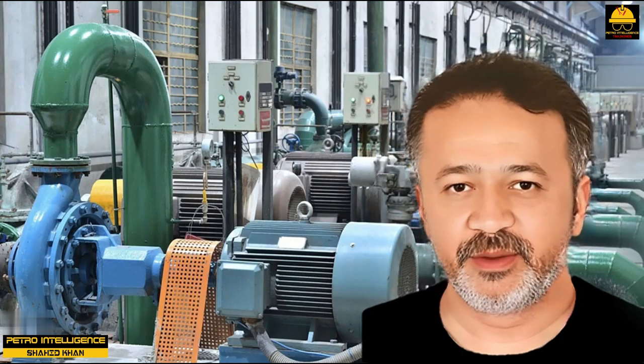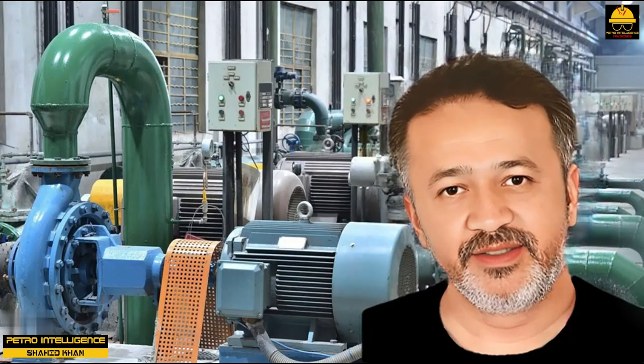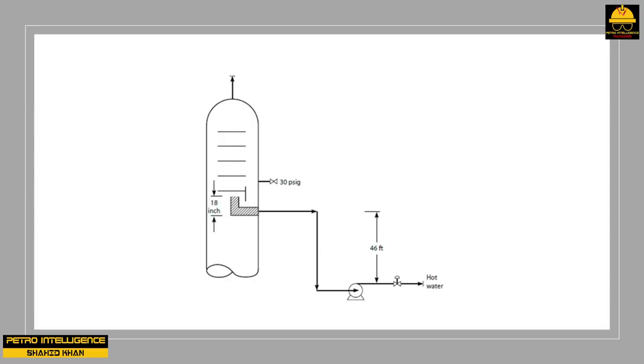Pumps cavitate for three reasons: insufficient available NPSH to satisfy the conversion of pressure to velocity in the eye of the impeller (running NPSH); insufficient available NPSH for the conversion of pressure to acceleration in the suction line during startup (starting NPSH); and the most common reason in the author's experience — partial plugging of draw nozzles. This is illustrated by a side draw-off from a fractionator, where slowly opening the discharge control valve increases flow up to a point, beyond which discharge pressure and flow become erratically low, indicating cavitation.